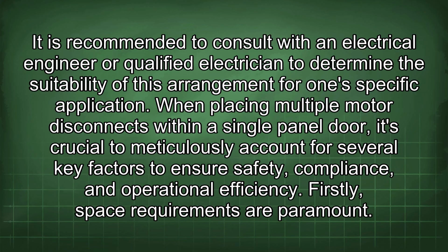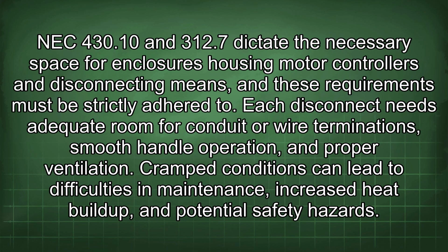When placing multiple motor disconnects within a single panel door, it's crucial to meticulously account for several key factors to ensure safety, compliance, and operational efficiency. Firstly, space requirements are paramount. NEC 430.10 and 312.7 dictate the necessary space for enclosures housing motor controllers and disconnecting means, and these requirements must be strictly adhered to. Each disconnect needs adequate room for conduit or wire terminations, smooth handle operation, and proper ventilation. Cramped conditions can lead to difficulties in maintenance, increased heat buildup, and potential safety hazards.